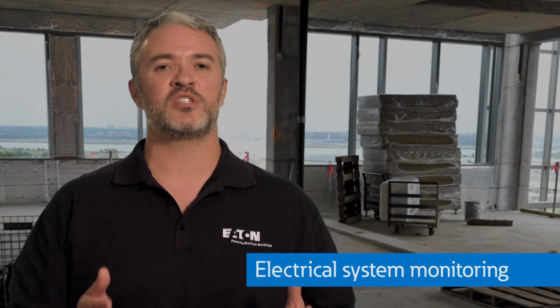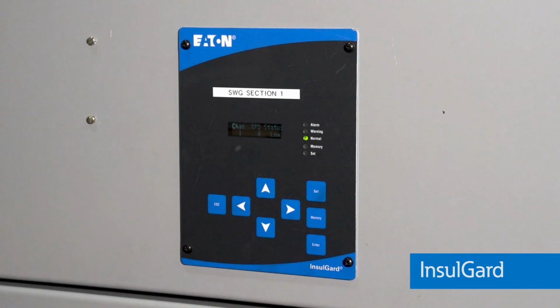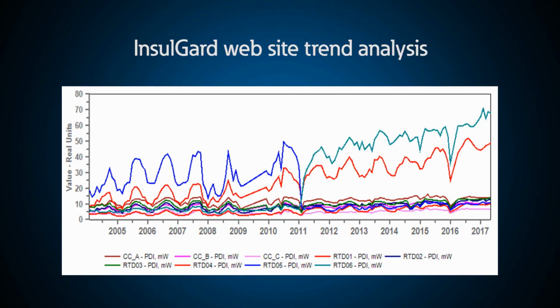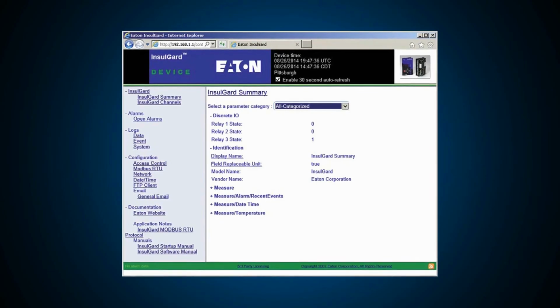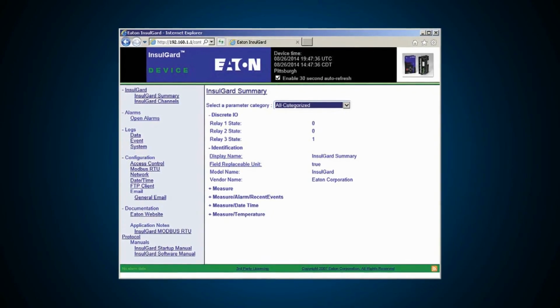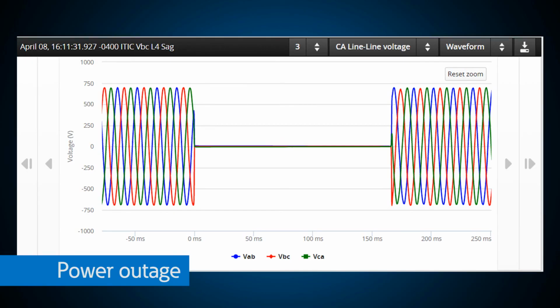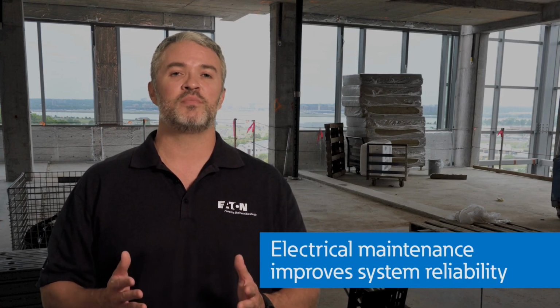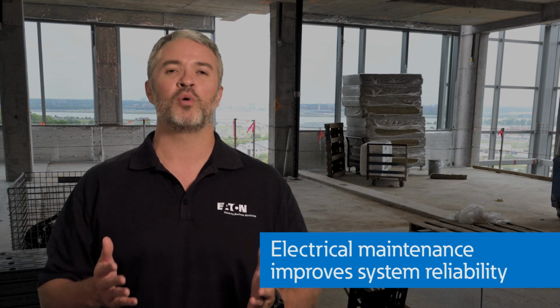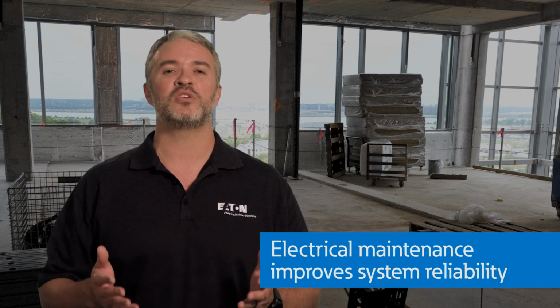Because of the critical nature of a hospital, electrical system monitoring is important to be able to see the power system from a centralized location. This allows hospital personnel and you as a contractor to remotely see alarms and potential problems as they occur on the essential electrical system. These systems can also prove beneficial for event analysis. If a full power outage occurs, the ability to trace the events that led to the failure is a key factor in protecting against liabilities. Electrical systems must be maintained properly to avoid poor performance, abnormalities, or outages and failures.